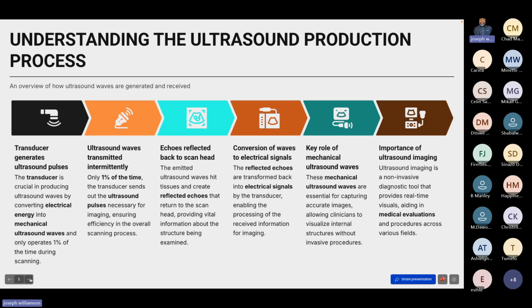So the electronics in that thing are mostly dedicated to interpreting and listening to the sound as it comes back. The echoes that are reflected back to the transducer are the ones that we shape. Rarely do we get to shape in any way, shape, or form, unless we're talking about power, the echo that's leaving. It's the one that's coming back that we can actually choose how we see it, what brightness it is, what wavelength is coming back at us, if we're using dynamic wavelength or not. It's the reflected echo that returned to the scan head that we shape. And we provide vital information by learning how to manipulate those echoes as they come back.